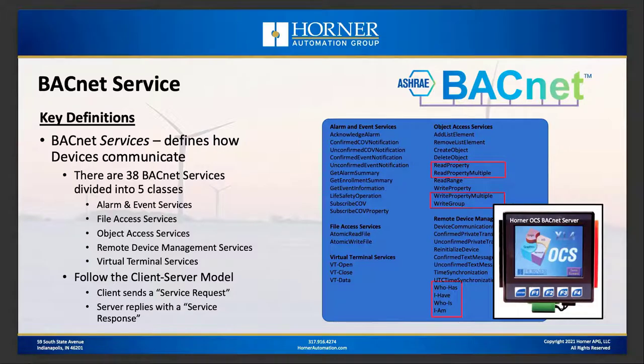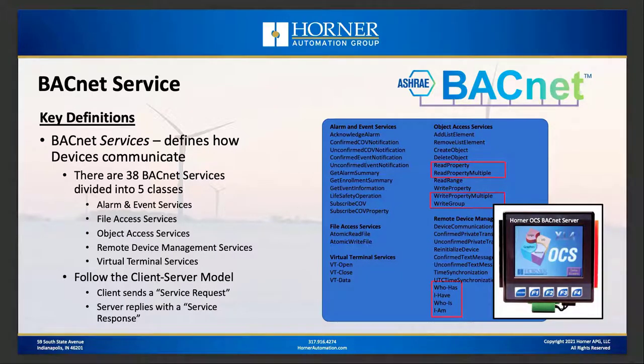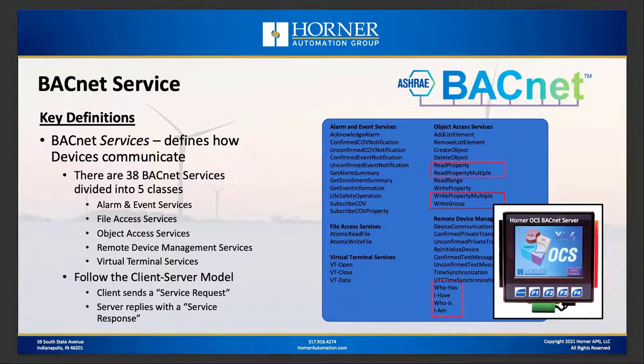Services define how devices communicate with each other. There are many different services divided into classes, and regardless of which service is in use, it follows the client-server model. One device acts as the client sending a service request; the other acts as a server responding with a service response. The OCS is always a server — it never acts as a client. It's not managing the building management system; you can think of it kind of as a slave on the network.